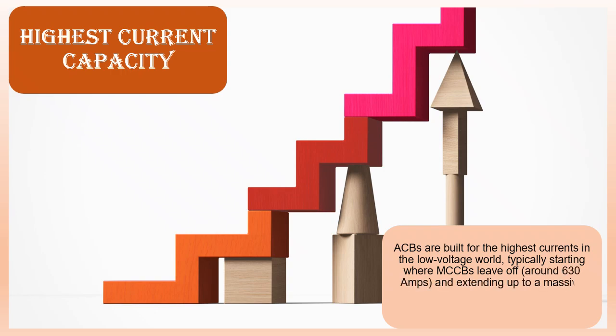Highest current capacity. ACBs are built for the highest currents in the low voltage world, typically starting where MCCBs leave off, around 630 amps, and extending up to a massive 6,300 amps. They handle the main incoming power feeds for large facilities.